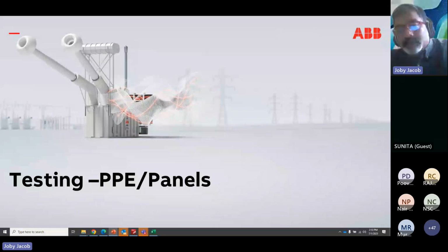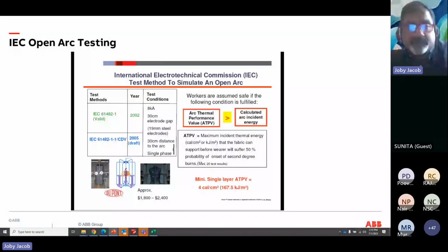A little bit on the testing side. There are various types of testing. The recent testing is IEC 62271-200, where you use, it's not in my slide, a slightly old way, the open box test, which we are doing. The new test method also considers the panel size, vertical or horizontal panels, and the depth, and all those things. So that's the standard. So it is the panel test basically.